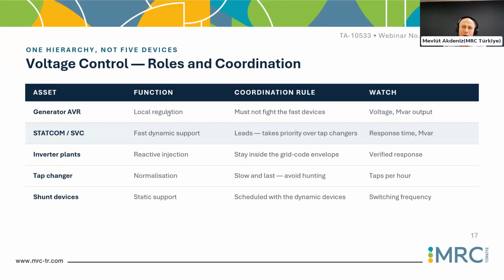As I mentioned, the reactive power issue is not a new one, but a very classical basic problem, but it's emerging. There are many typical solutions for that problem. They all contribute to a similar purpose, but in different ways. The generator AVRs are the basic ones, especially for synchronous generators. If I have rotating machines, we try to benefit from all the features they have. They have overload capability, overshoot capability, short circuit contribution, even some oscillation damping capability, and with large inertia the first inertial response is also good. So we will be using these synchronous generators as much as possible.